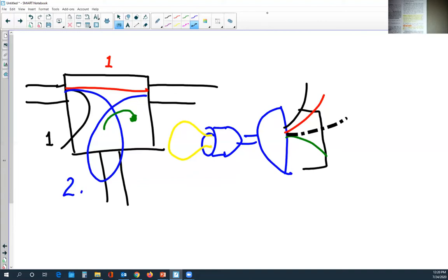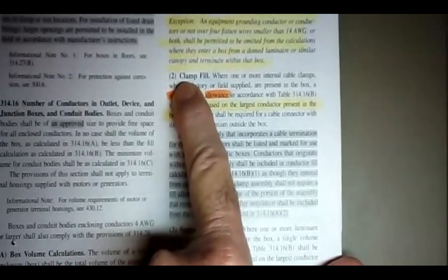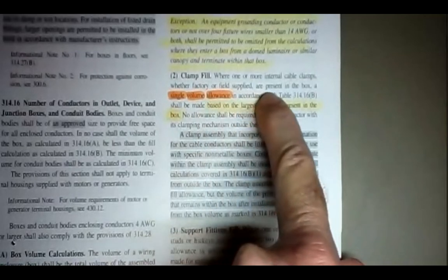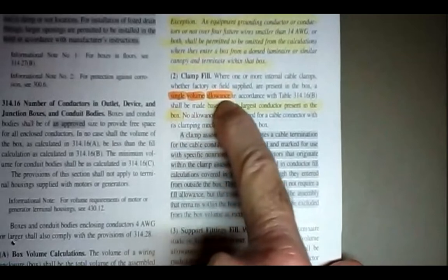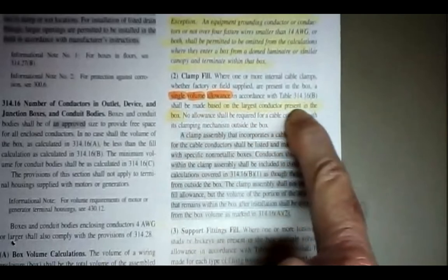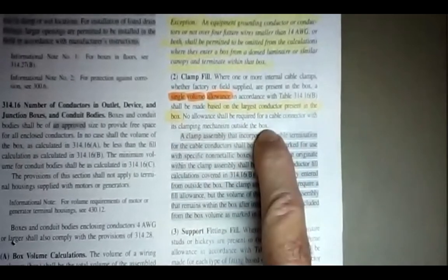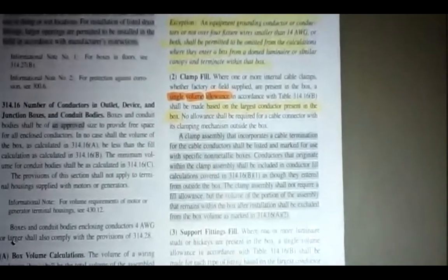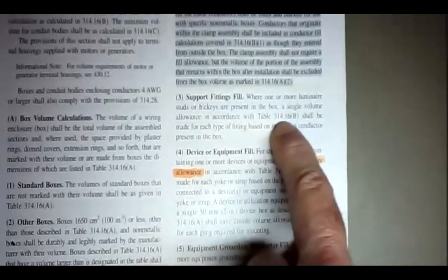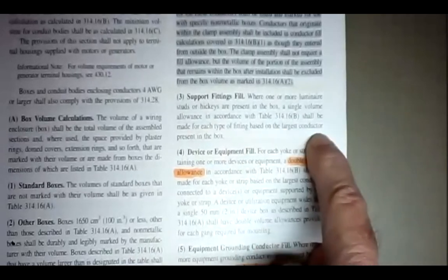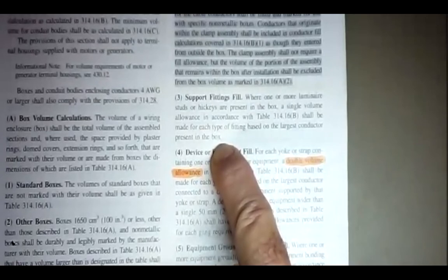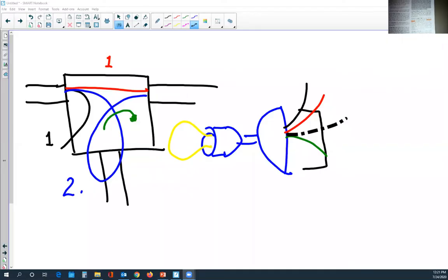For clamp fill: where one or more internal cable clamps, whether factory or field supplied, are present in a box, a single volume allowance per table 314.16B shall be made based on the largest conductor present. No allowance is required for a cable connector with its clamping mechanism outside the box. For support fittings: where one or more luminaire studs or hickeys are present in a box, a single volume allowance per table 314.16B shall be made for each type of fitting based on the largest conductor present. Let's go back to the smartboard to look at what we just covered.